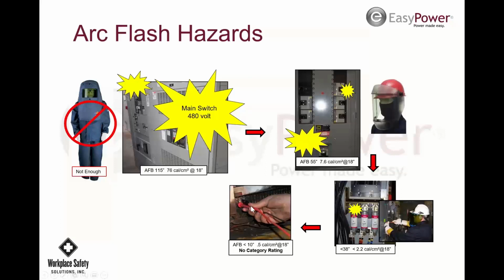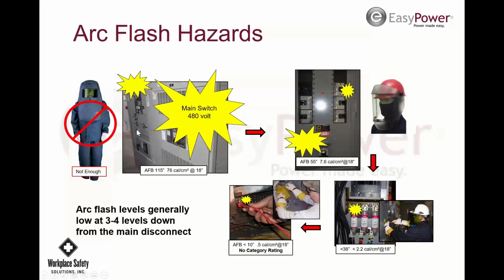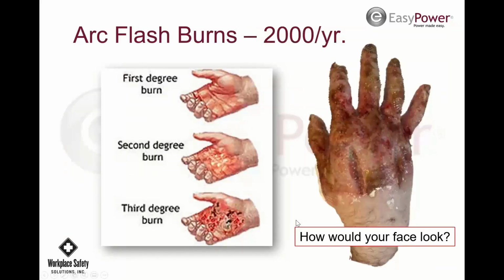And rubber gloves with leather protectors would have protected him from the arc flash as well as the shock. So that's what the study kind of looks like. Usually 3 levels down, 1, 2, 3 is down to now. This is a higher level at the main, but downstream from the main, these levels are usually at a low level, usually 3 levels down generally. This is just arc flash burn.